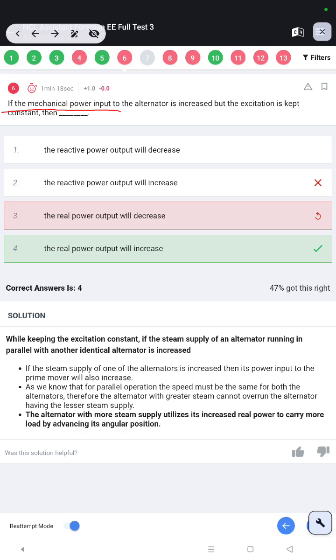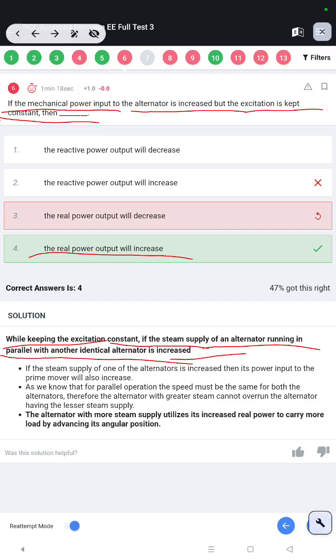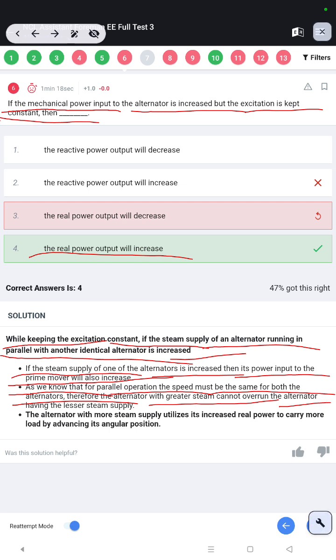If the mechanical power input to the alternator is increased but the excitation is kept constant, then the real power output will increase while keeping the excitation constant. If the steam supply of an alternator running in parallel with another identical alternator is increased, if the steam supply of one of the alternators is increased, then its power input to prime mover will also increase. As we know that for parallel operation the speed must be the same for both the alternators. Therefore, the alternator with greater steam cannot overrun the alternator having the lesser steam supply. The alternator with more steam supply utilizes its increased real power to carry more load by advancing its angular position.